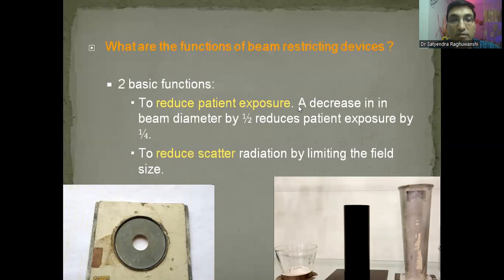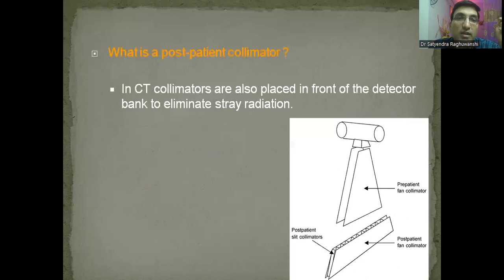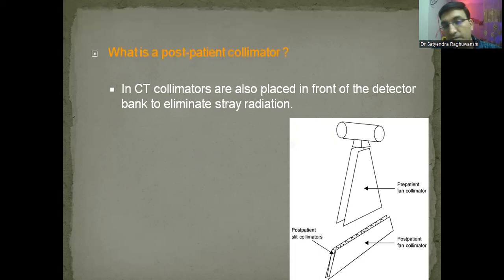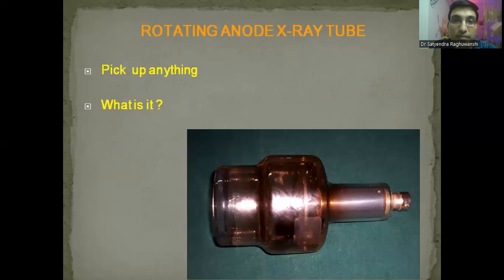What is the construction? The base is made of lead and the body is lined with copper, which aids in absorption. Collimators are sheets of lead — you will generally not find collimators in the table viva. In CT scans we also use pre-patient and post-patient collimators. Do the exposure factors change with beam restrictors? Yes — as with grids, a little bit of exposure factors have to increase to maintain film density.